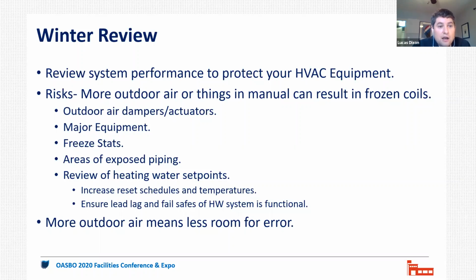Things like, did we put our outdoor air dampers in manual at 100% open? With those dampers open nearly all the time, are the actuators still working, since they may not have been exercised or opened and closed in several months? Did we prop open or mechanically lock out or lock open any actuators to maximize outdoor air?